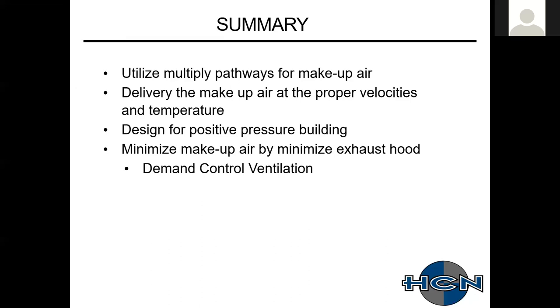And then the biggest thing for hood systems, if you want to minimize your makeup air, is to minimize your exhaust flow rates. So that means designing with a listed hood and getting that equipment lineup of what the kitchen staff is using. So we can say, hey, instead of having a broiler on the left-hand side of the hood and an oven in the middle, if we flip that around, put the oven on the left-hand side and put that broiler in the middle where that exhaust riser is, it's an easier capture and contain when you have that heavier duty appliance towards the middle and your lighter duty appliances towards the end. Or if you're utilizing walls, putting a hood right up against an L shape of a wall is definitely going to help because you're creating a natural end panel for that hood system. So instead of having three open sides, you actually only have two.